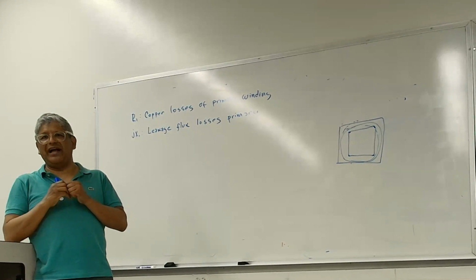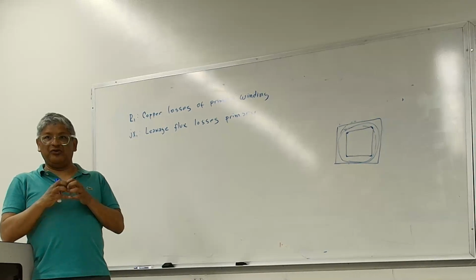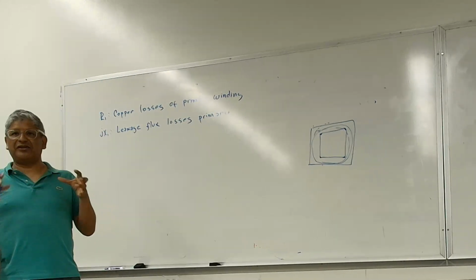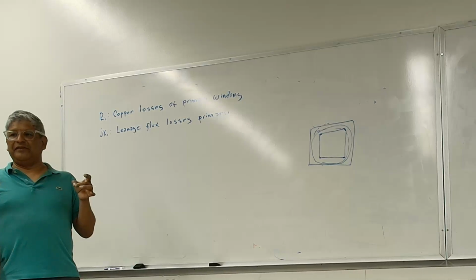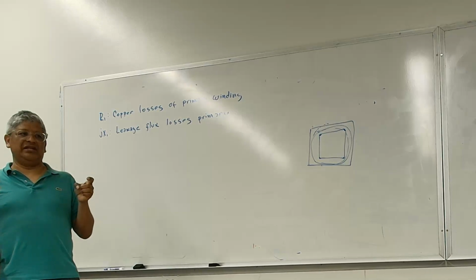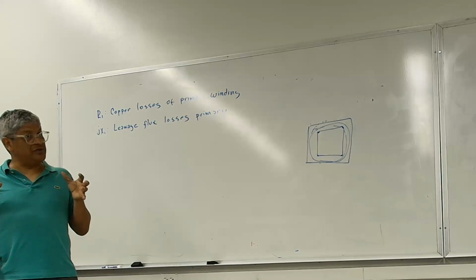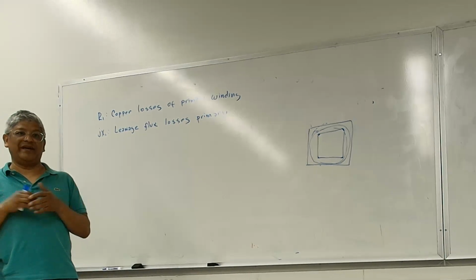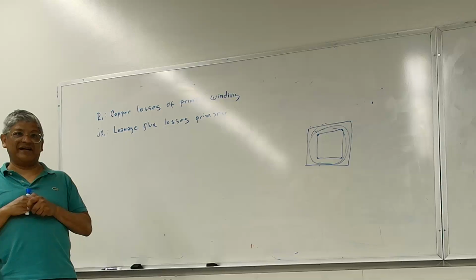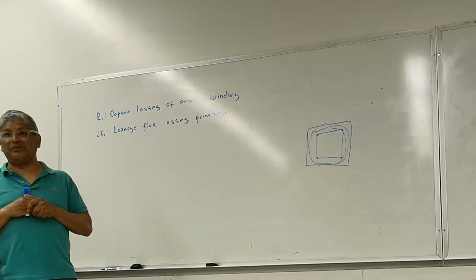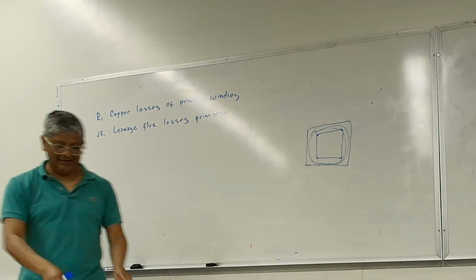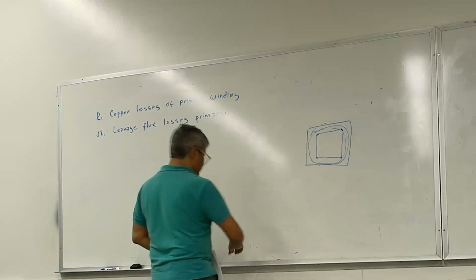You're always going to have some leakage. But if you cannot manage the geometry in manufacturing, it will turn into reactive losses, which is not what the customer wants. So that's part of how precise the design is.